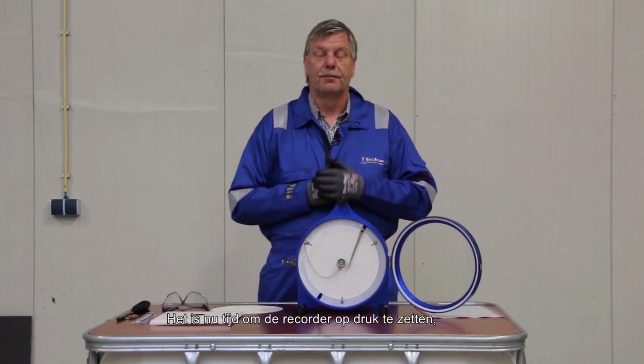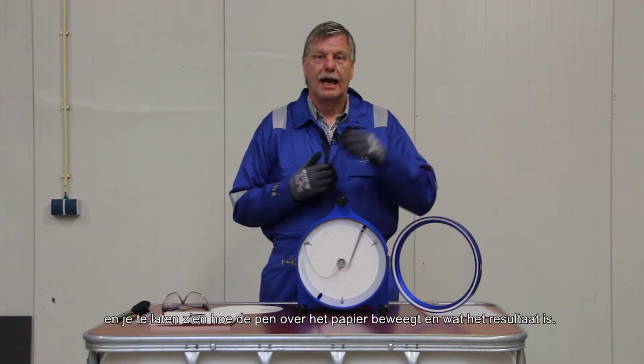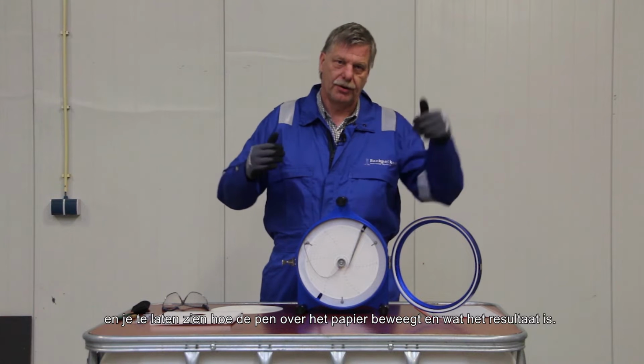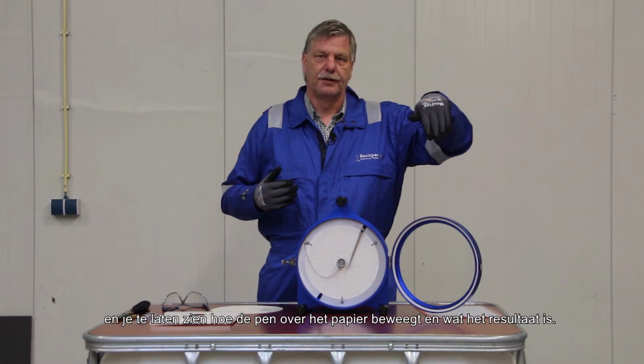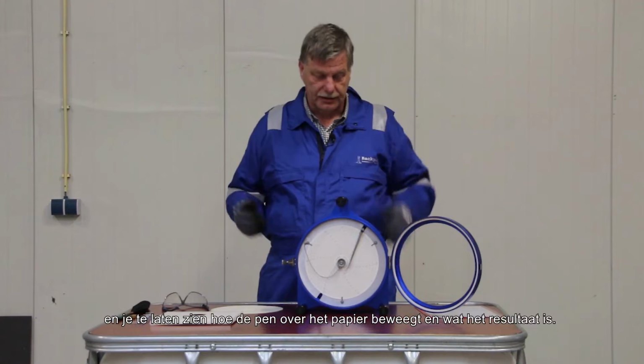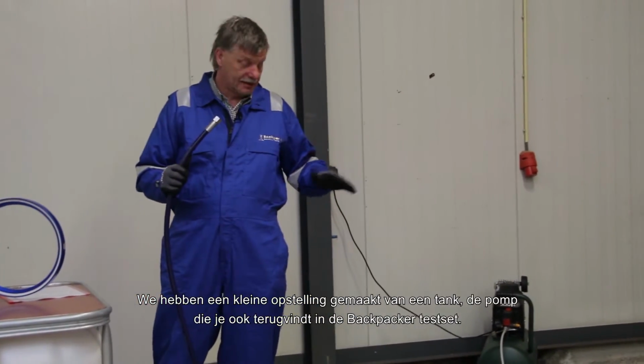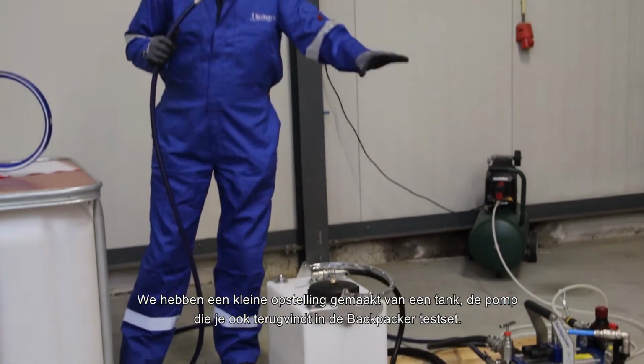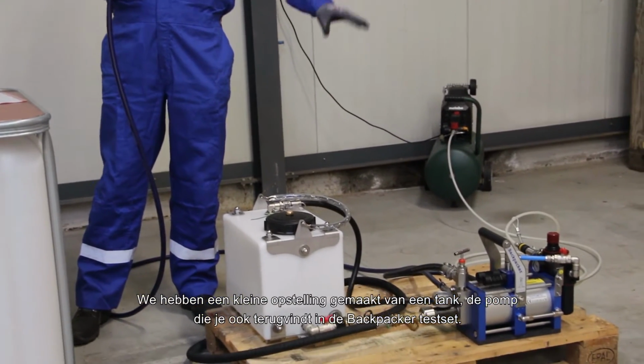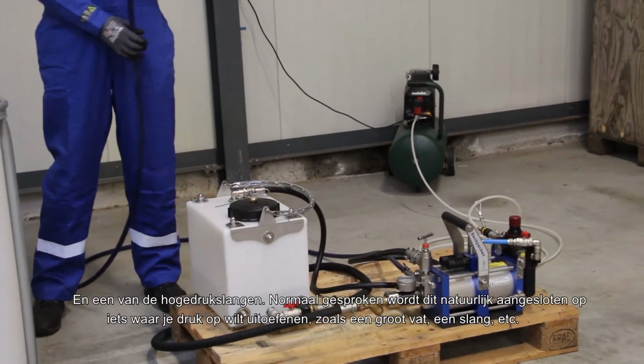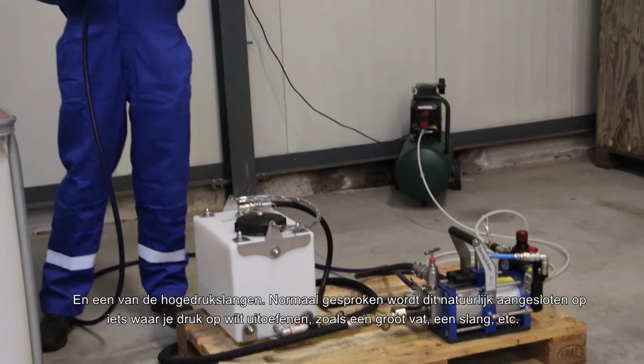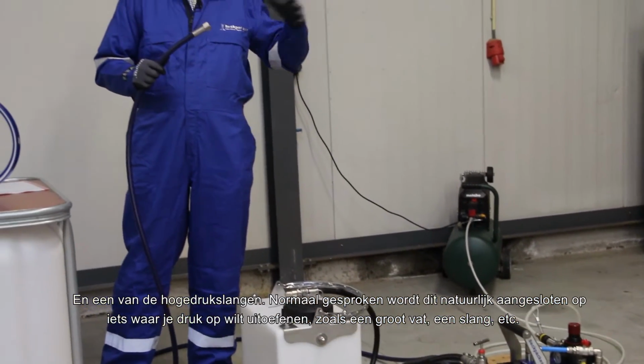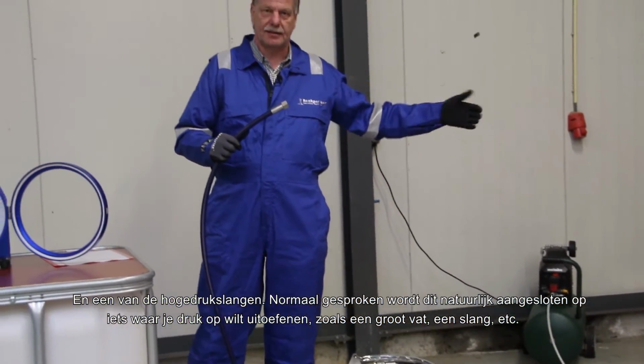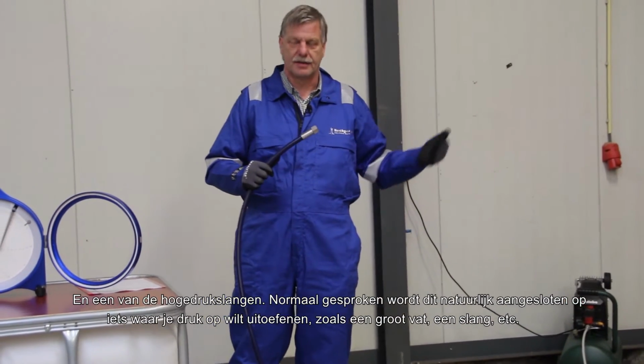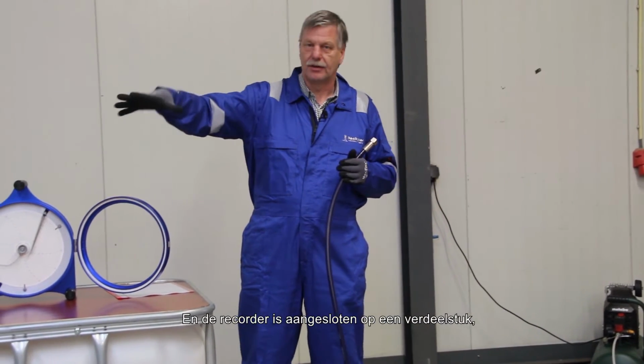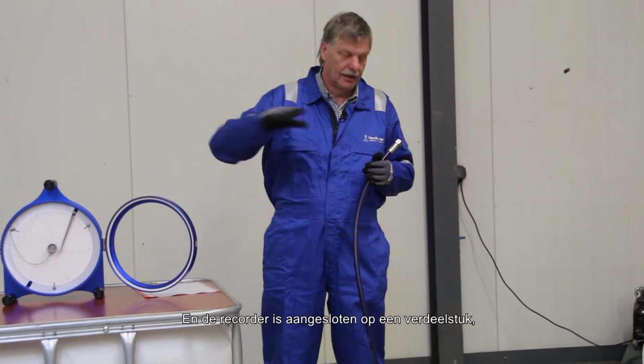It's now time to apply some pressure on the recorder and show you how the pen moves over the paper and what the result is. We've made a small setup with a tank, the pump that you'll also find in the Backpacker test set, and one of the high pressure hoses. Normally this would connect to something you want to pressure test, like a large vessel or a hose, and the recorder is connected to a manifold.